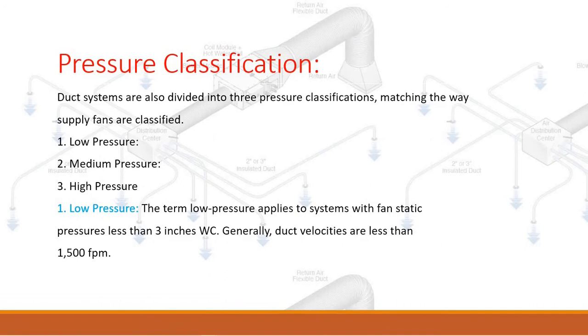Pressure classification. Duct systems are also divided into three pressure classifications matching the way supply fans are classified. One: low pressure, two: medium pressure, three: high pressure. Low pressure applies to systems with fan static pressures less than three inches WC, and generally duct velocities are less than 1500 FPM.